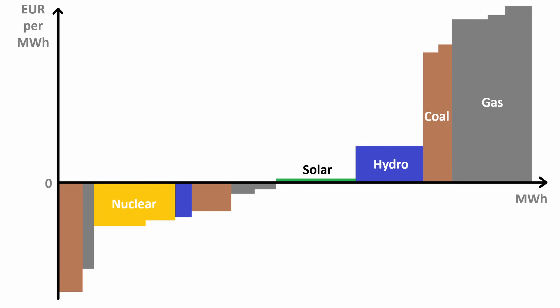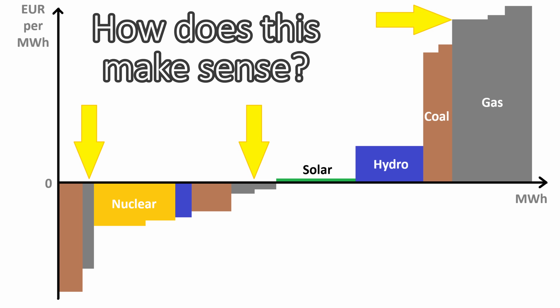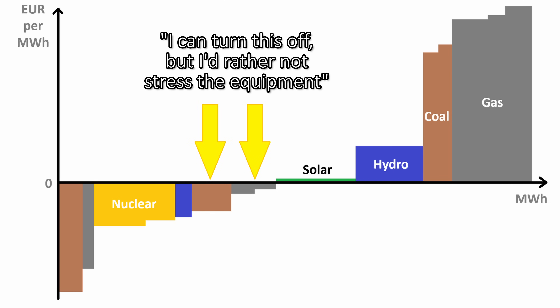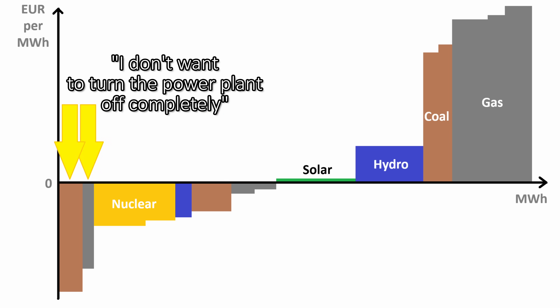Here comes the unintuitive part. The lowest price that a generator might be willing to sell for is not necessarily the price at which it will achieve a positive contribution margin. So if making 1 MWh costs you a minimum of 8€ in natural gas, that does not necessarily mean every single one of your MWh gets bid at 8€ or above. In fact, some of your MWh might even get bid at negative prices — such as negative 40€ per MWh. Why? Because for conventional power plants, turning the power up and down quickly is hard on the equipment and may be energetically inefficient. For example, temperature fluctuations cause stress from thermal expansion and contraction, and shutting the burner off completely means boilers and turbines cool to room temperature, wasting all the fuel needed to reheat them to minimum operating temperature.